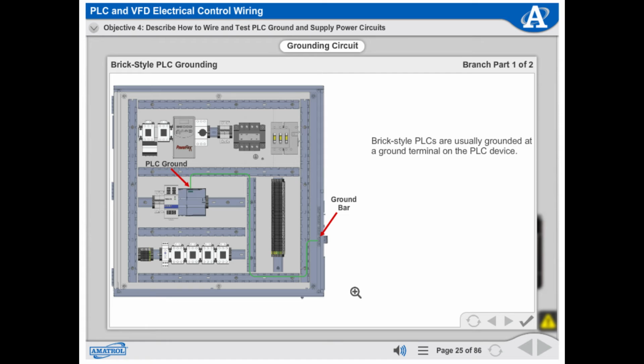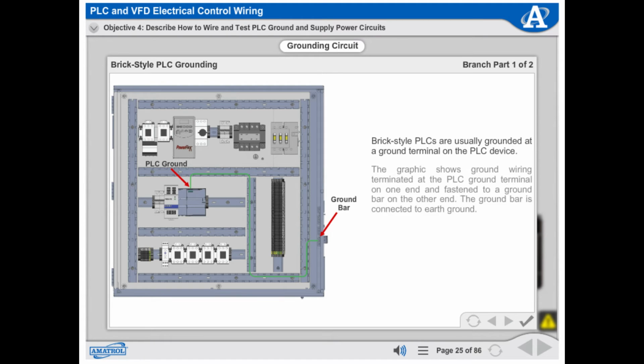Brick-style PLCs are usually grounded at a ground terminal on the PLC device. The graphic shows ground wiring terminated at the PLC ground terminal on one end and fastened to a ground bar on the other end. The ground bar is connected to earth ground.